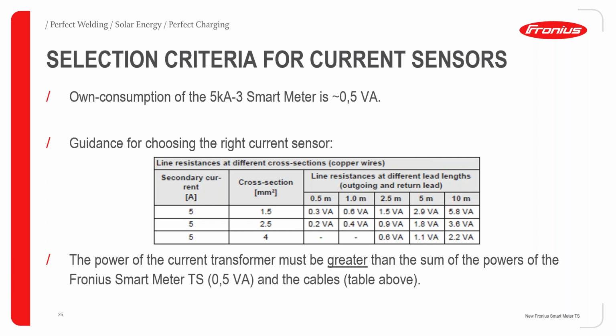So, what is the power of the Fronius Smart Meter? The own consumption of the 5kA-3 Smart Meter is 0.5 VA, so 0.5 watts. And then, what is the power of the cable? Because the sum of power of cable and the smart meter must be less. The current transformer power must always be greater.